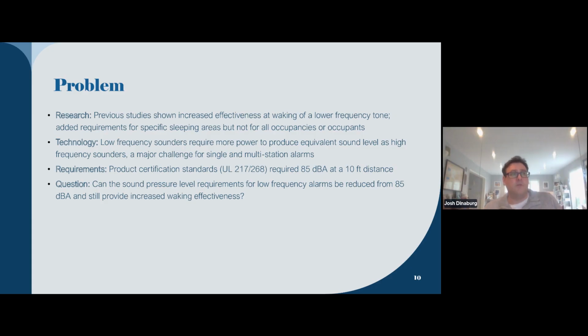Part of this trouble was the requirement for alarm devices to produce 85 decibels at this 10-foot distance. This is a pretty high level of sound, and it's required of all these devices. So the question NFPA Research Foundation wanted answered is, can we reduce the sound pressure levels required for the low frequency alarms from that 85 dBA? So it's a little quieter, it draws less power, it's more able to operate on a battery. And can we do that and still actually provide our waking effectiveness, still wake up at least equal to the amount of people we wake up now with the 85 dBA alarms, and ideally more people. So this is the question we started with as the basis for this research.